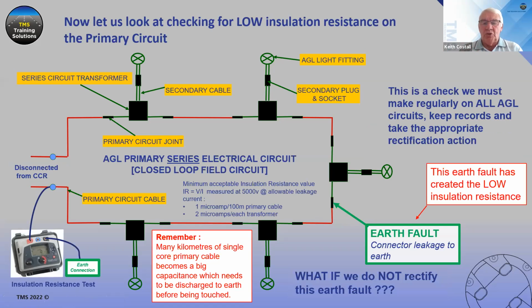To give us an earth fault, it's low insulation resistance. Now, this is not a training course, it's an awareness webinar. So what we do is frequently and regularly measure the insulation resistance of our field circuit. And when we do, we need to take the records and we do it against a standard. And that standard is associated with allowable earth leakage. But we would test it for compliance at 5,000 volts.